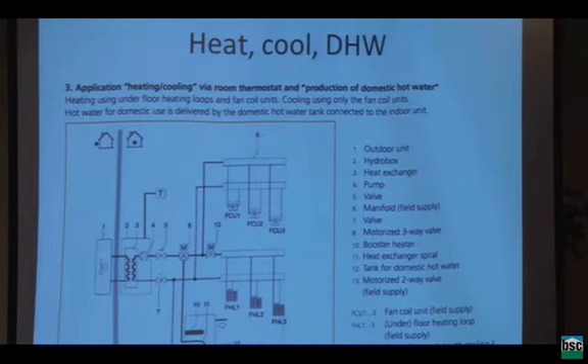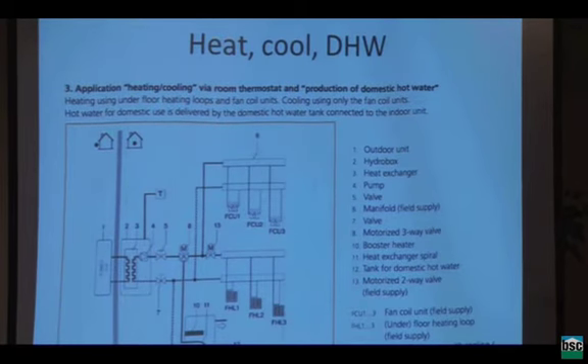The problem is that there is a desire, especially amongst engineers, to make a magic box. And as a consequence, we're often sacrificing performance by putting everything, heating, cooling, hot water, it slices, it dices, it makes julienne fries, and you put it into one product, you're going to lose something. But that said, people are looking for simpler solutions, and if they're complex but come in a factory-made box, it's not as bad. And I mean, Lloyd, we've talked about that too, about ground source heat pumps, is that if they come in a factory-made box, complexity isn't a big obstacle because they're going to make 10,000 of them. It's as soon as you have to wire some of this stuff or pipe it in the field is when it becomes a complete freaking disaster.